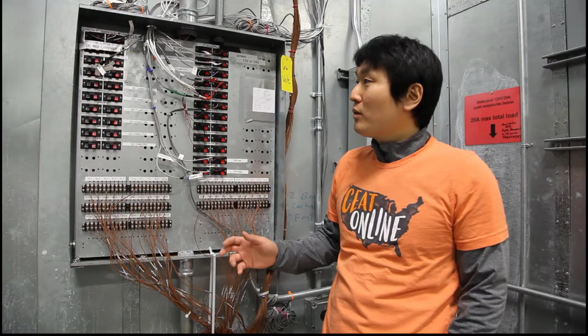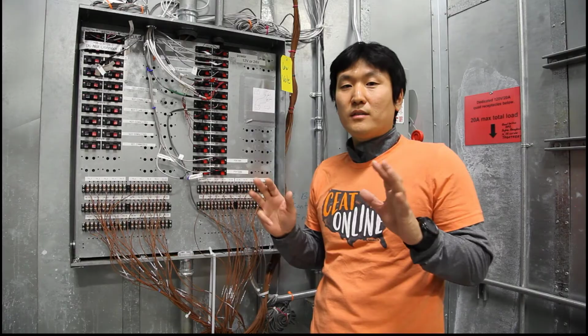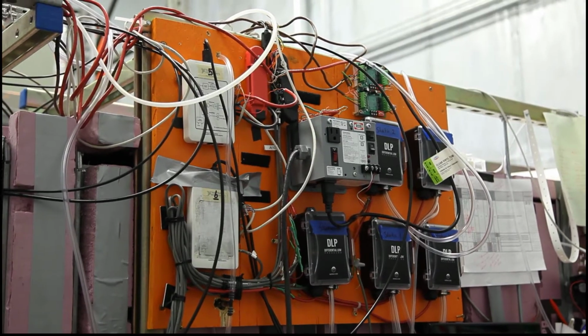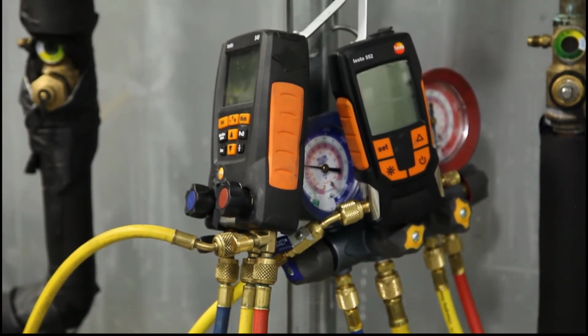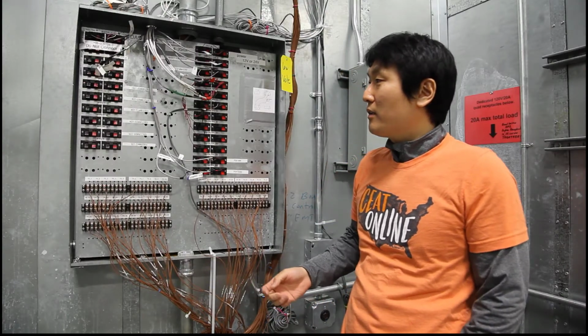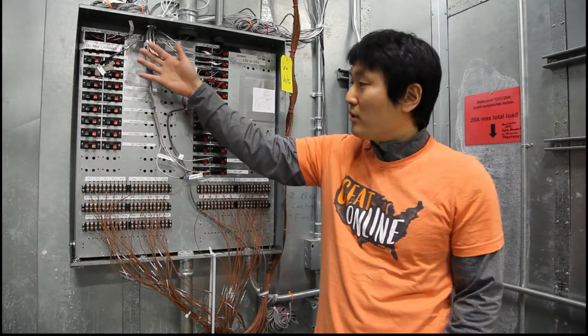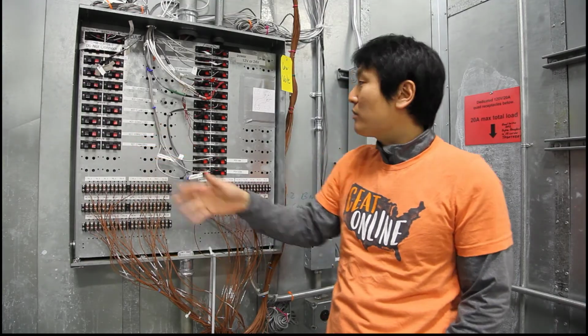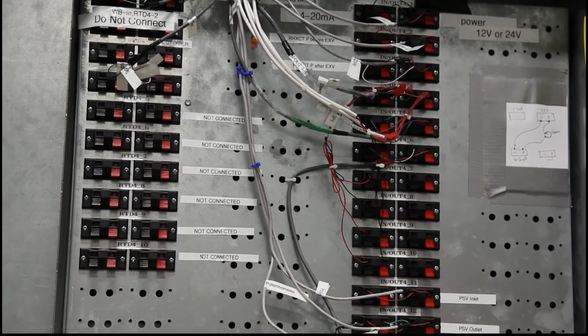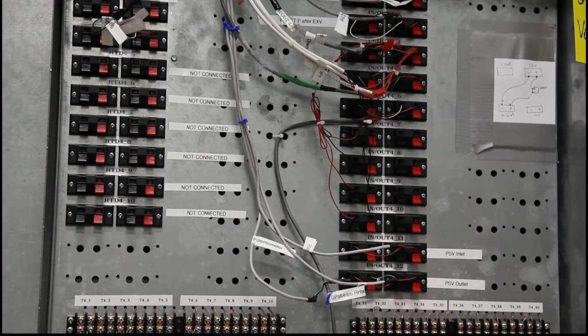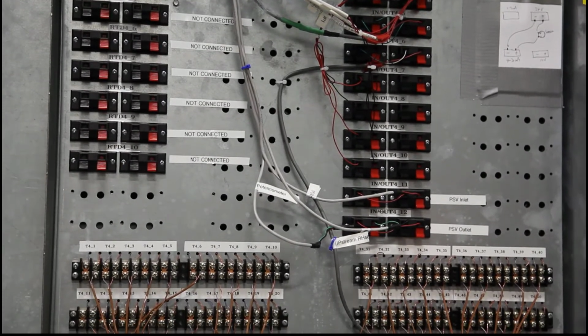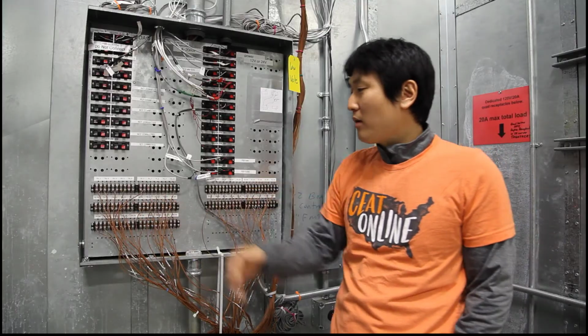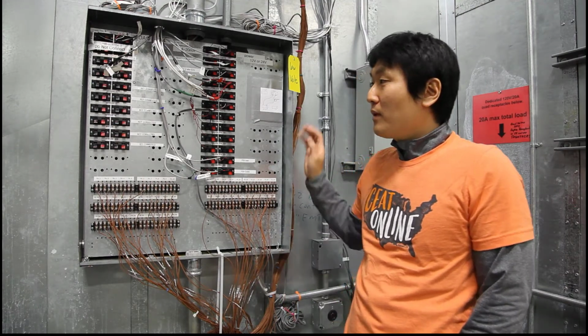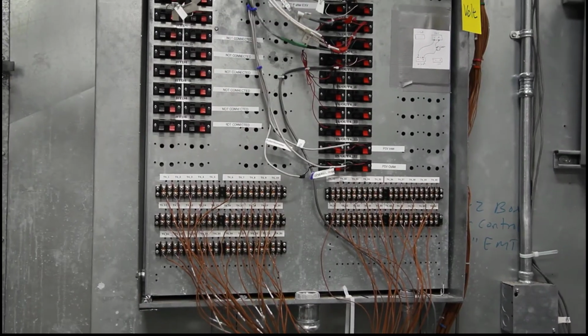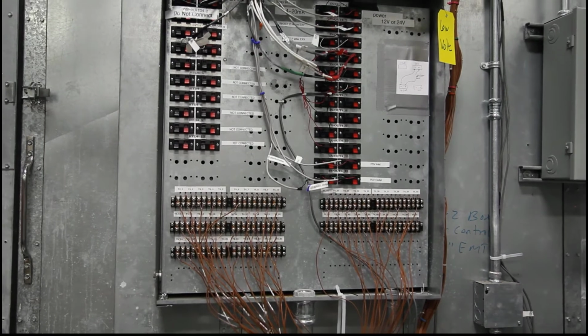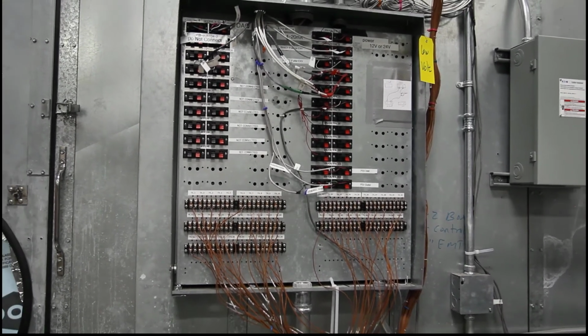For example, we have 8 DAQ boxes in the indoor chamber and outdoor chamber, and then outside the chamber as well, and that contains a lot of RTD sensors. The in and out ports can accommodate 4 to 20 milliamperes, and then 0 to 10 volts. As you can see, we have a lot of thermocouples. So we can say this psychrometric chamber can perform a lot of different projects at the same time as well.